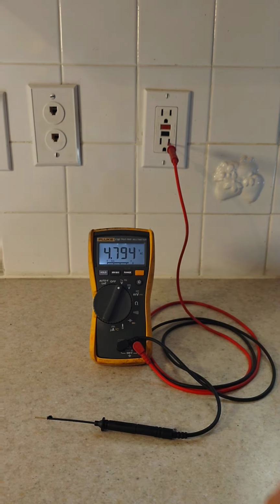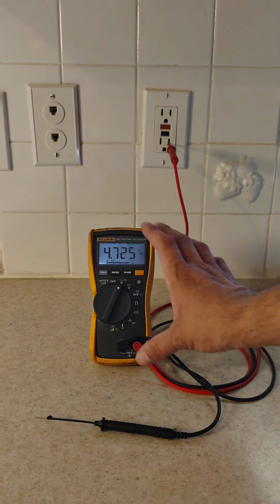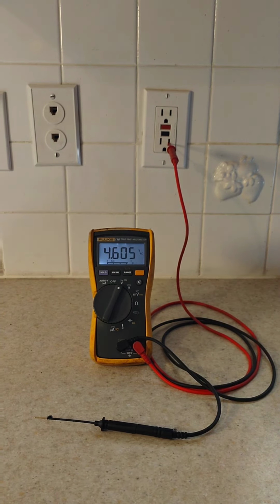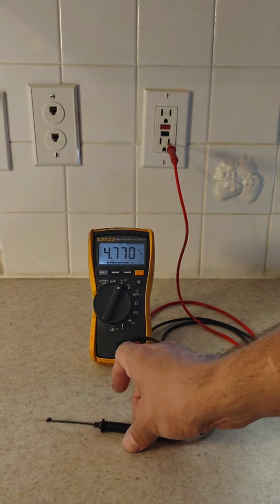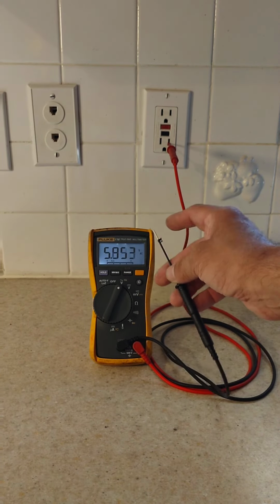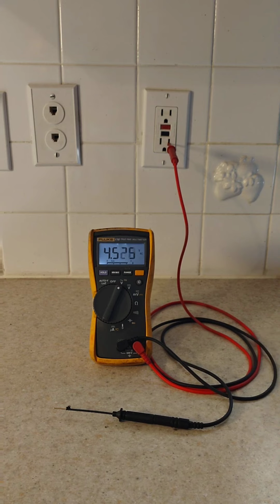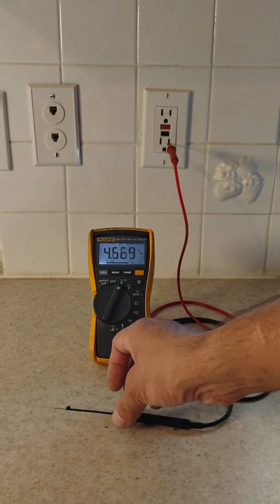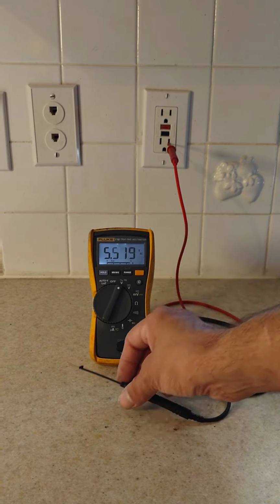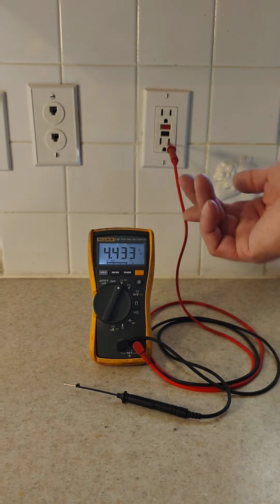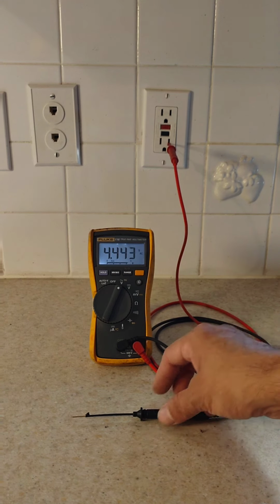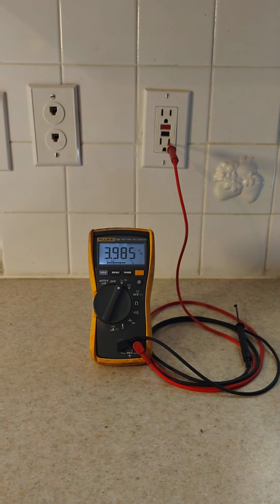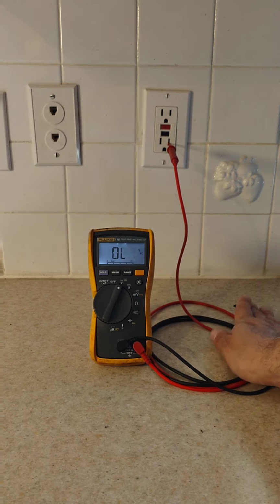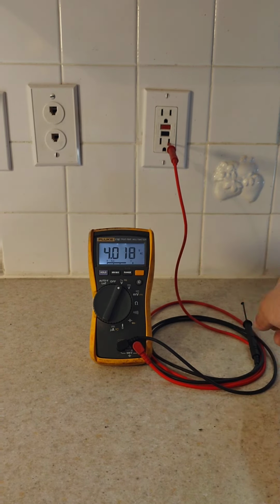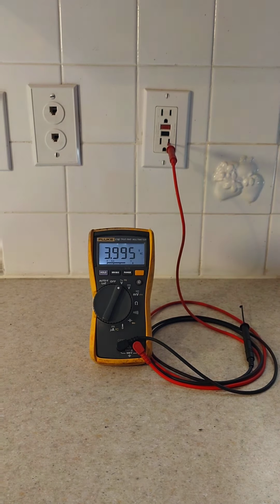This is showing ghost voltage, which means our meter is drawing so little power from the circuit, it has such a high input impedance, is the term of art, that it's showing voltage that doesn't actually have the capacity to do any work. And what that means in practice is usually that we have an open neutral, which is exactly what we're showing here. This black probe is actually acting as an antenna, and it's coupling with the environment to give a ground reference for our red probe.